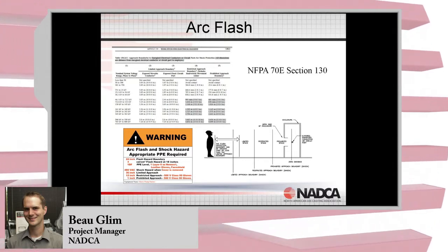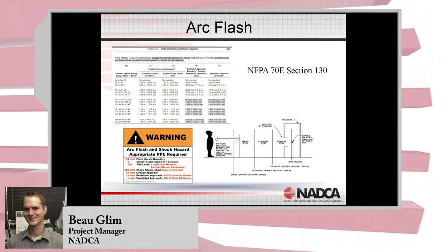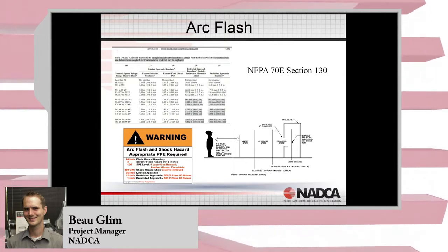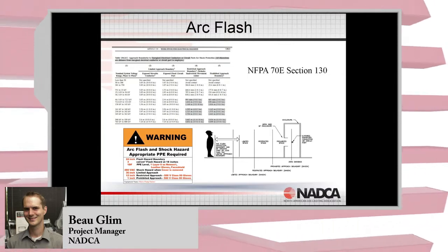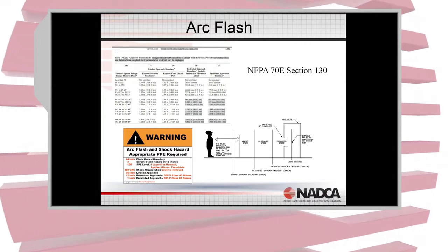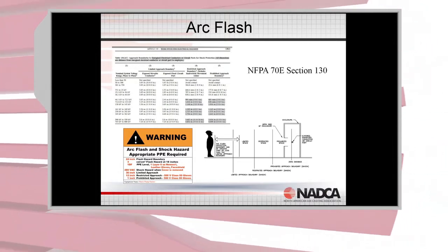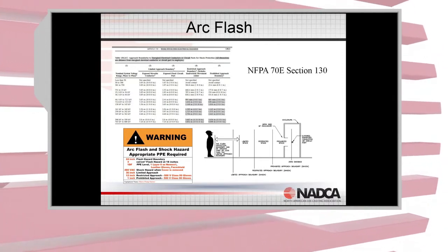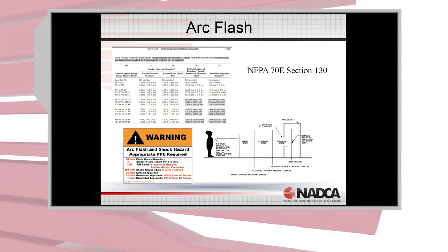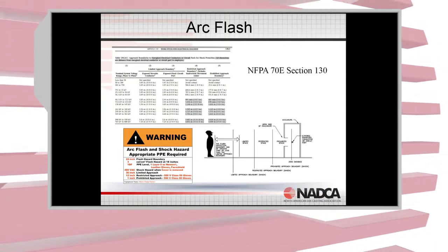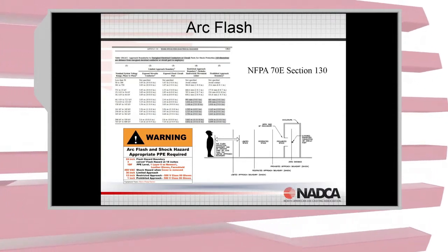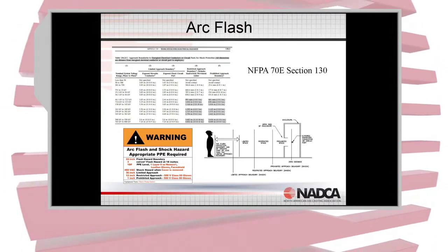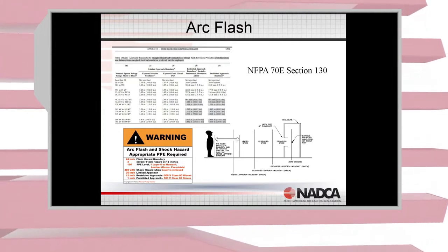You can either take the formulas from NFPA 70E and IEEE standard 1584, or there is an IEEE spreadsheet-based calculator. Or if you really want, there are commercial software packages available that will calculate that for you. And you just take that data and determine, okay, here's where the boundary should be. And if you have that, make sure you put a sticker up there alerting people of what those boundaries are and what PPE they need to wear to go inside those different zones.